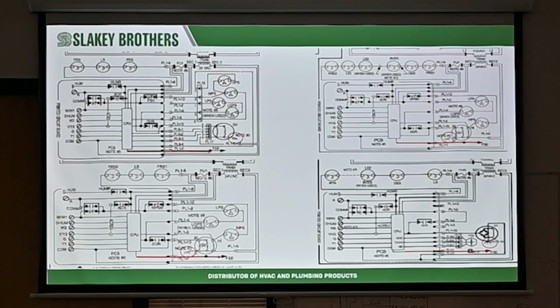Again, it doesn't show the high voltage side because this is a 24 volt circuit. Make sure it's got a good ground. To make sure you got a good ground, I simply would just go sheet metal to L1, and if I got 120, I'm working. And that means I should have a good ground overall, okay? If I don't have it, or if I have low voltage, like only 60 volts, 70 volts, I better check out my outlet. Maybe the outlet's my problem, why I'm not sensing the flame. Anytime you check, hot leg to neutral, 115, 120, hot leg to ground, 115, 120. That's how you confirm that your ground should be good.